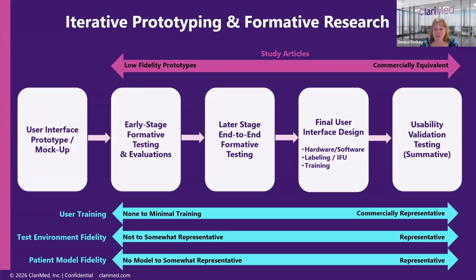Sure. A user interface is actually anything that an end user sees, hears, feels. That's not only the hardware and the software, but it's the labeling, the instructions for use that are part of the labeling, the on-package labeling, and the training program. All of those components are considered the user interface. So they should all be evaluated early on, maybe separately, but then later on as a full package in order to ensure that you can safely and effectively use your products. Thank you for bringing that question up, Angelina. I think that was great.